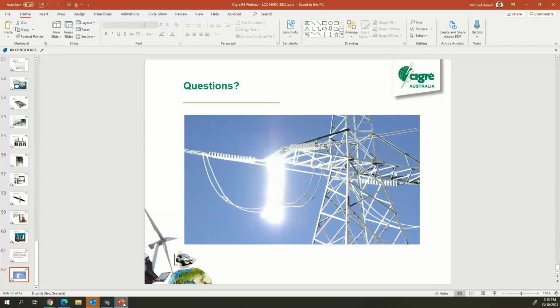Those are the main issues I see, because even with our cables, our cables are 40 kilometers long. I mean, that's like nothing compared to Sun, what they're talking about with Sun. Ours is pretty much nothing compared to Basslink as well, but we do a 24/7 patrol over our cables. We've got a cable protection zone. It's in New Zealand law. If you go fishing there or dropping anchor, you can be prosecuted under the law.